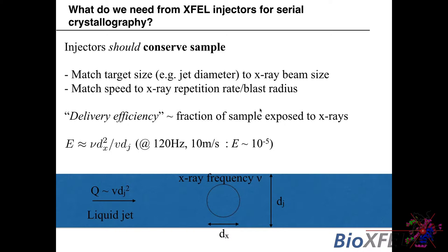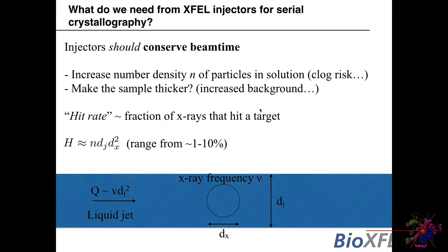The injector also needs to conserve sample. We need to roughly match the injector size to the x-ray beam size, and match the injection speed to the blast radius and pulse repetition rate. A critical parameter is delivery efficiency — geometrically, it's the fraction of sample exposed to x-rays. For a liquid jet moving at 10 meters per second at LCLS (120 Hz) with a micro-focused beam, the delivery efficiency is roughly 10^-5, which is startling. One approach is to slow it down, as the LCP injector does, though at higher rep rates that speed may be needed.